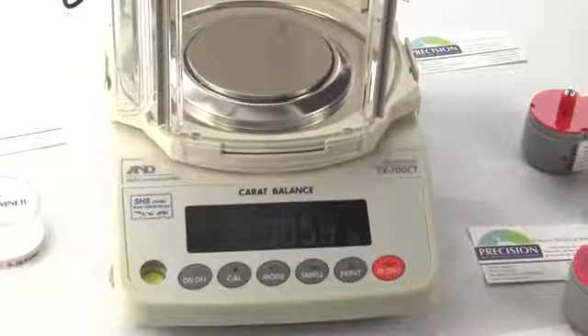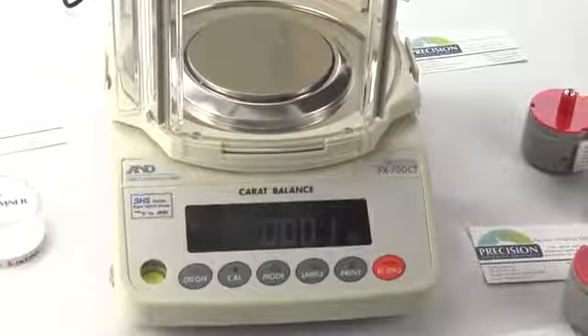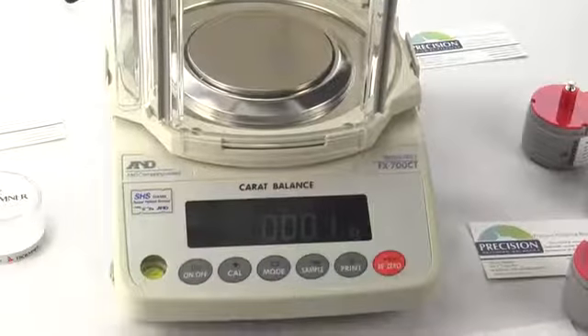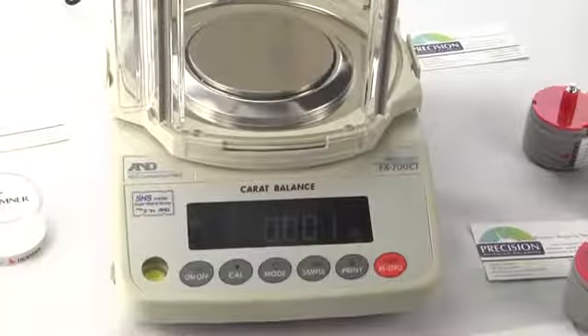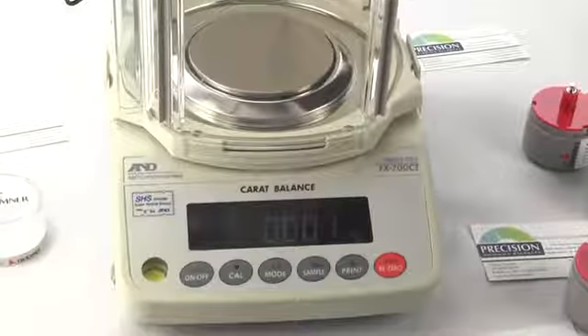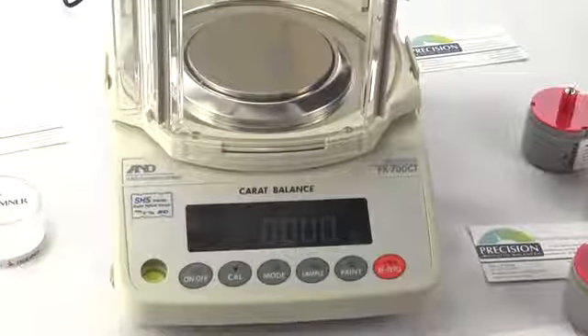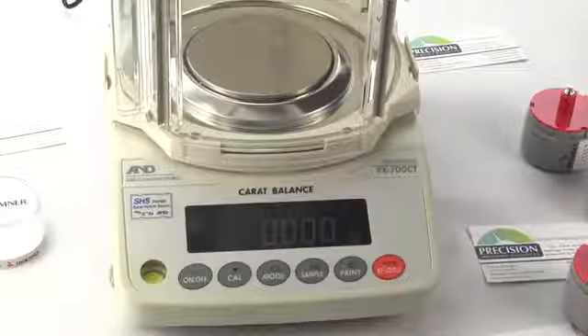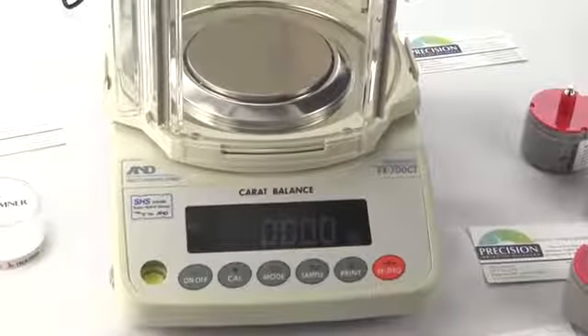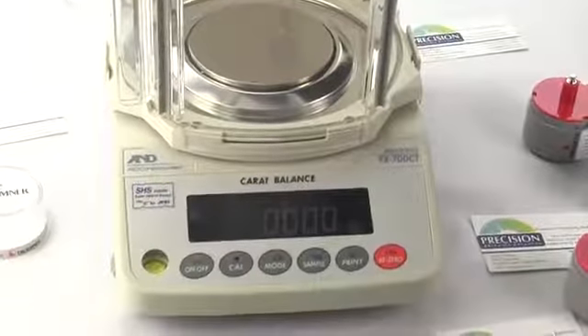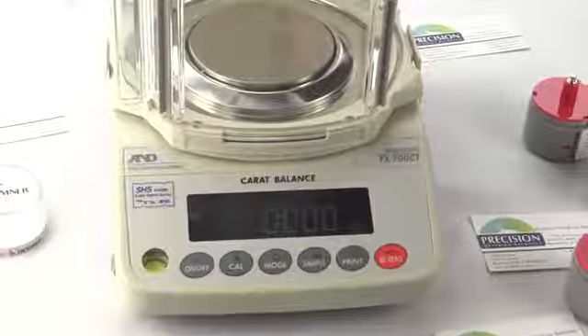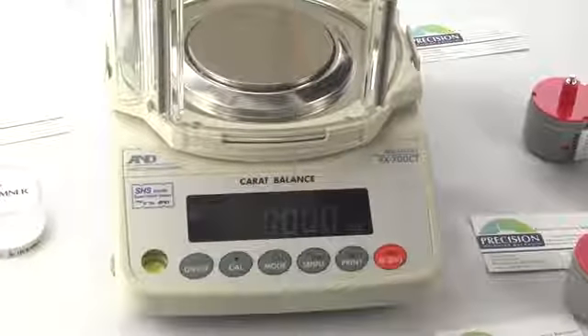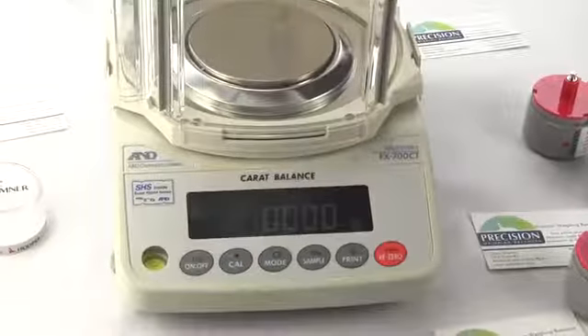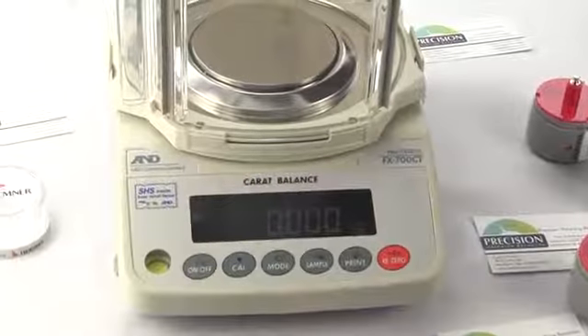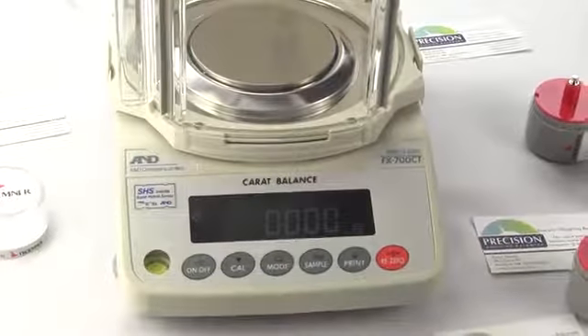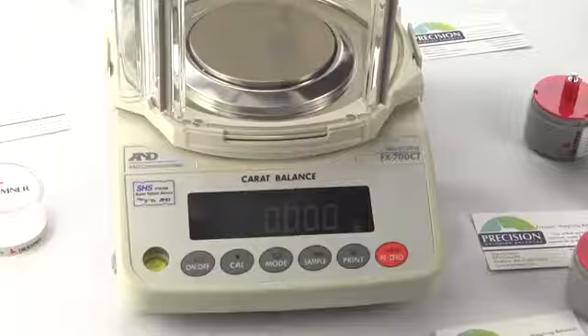The FX-700CT offers the ability to perform calibration using a choice of 4 different cal weights. So in this particular balance, you can calibrate with a 150, a 100, a 50, or a 20 gram calibration weight. The default out of the box is 100 grams. You can visit our other website for cal weights, which is calibrationweight.com, to see the full line of calibration weights we offer. So let's do a calibration using the default setup.